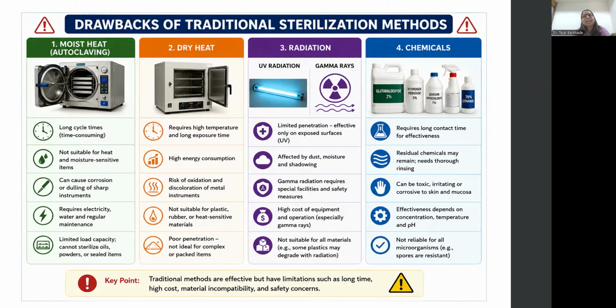For example, if I want to sterilize any plastic material in an autoclave or by using moist heat, I cannot do it because the mechanical property of that particular plastic material can be changed. So this is a very important drawback here. Heat sensitive material we can't sterilize using moist heat, and it can also cause corrosion or dulling of sharp instruments. It requires electricity, water, and regular maintenance, and is limited to load capacity; it cannot sterilize oil, powder, or sealed items. So these are the drawbacks of using moist heat for sterilization.